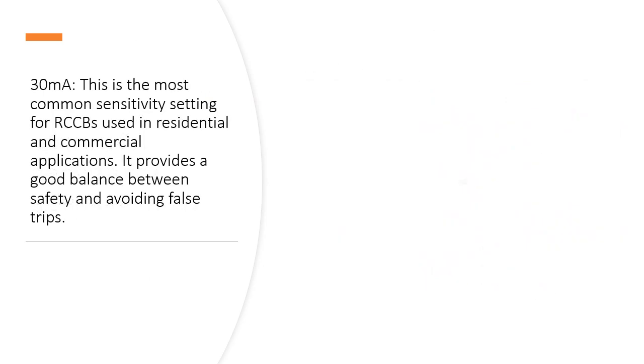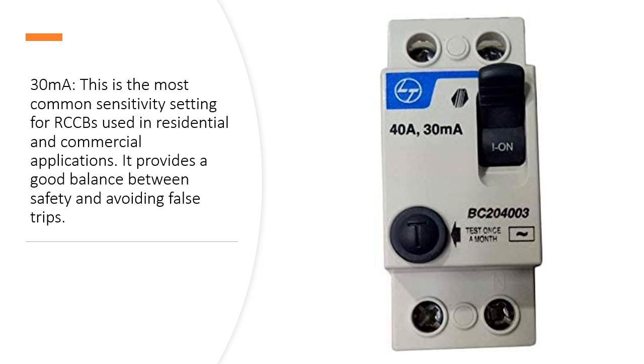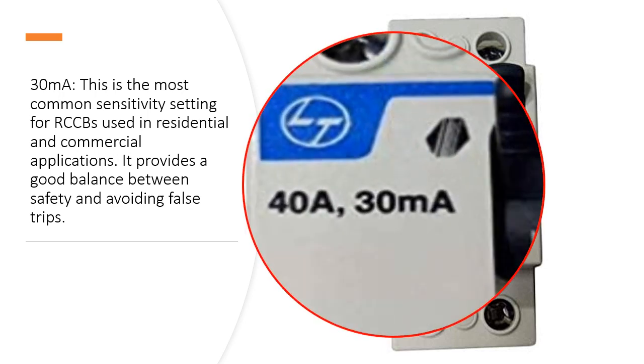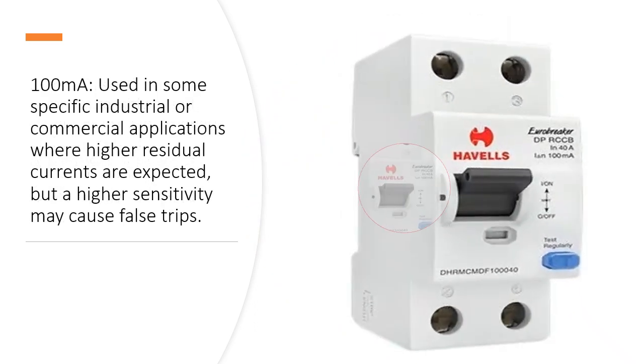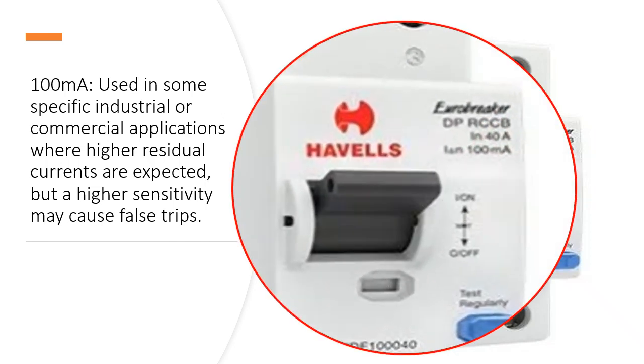Common RCCB Sensitivity Settings include 30mA, which is the most common sensitivity setting for RCCBs used in residential and commercial applications. It provides a good balance between safety and avoiding false trips. 100mA is used in some specific industrial or commercial applications where higher residual currents are expected, but a higher sensitivity may cause false trips.